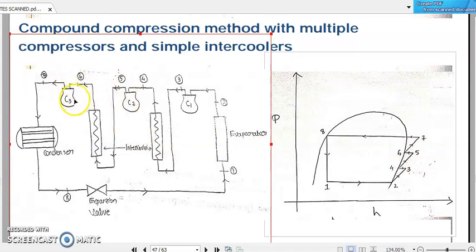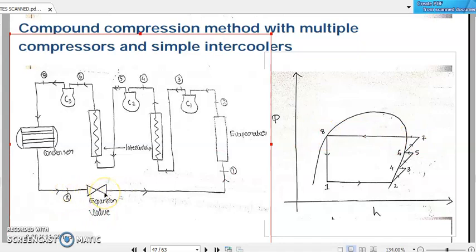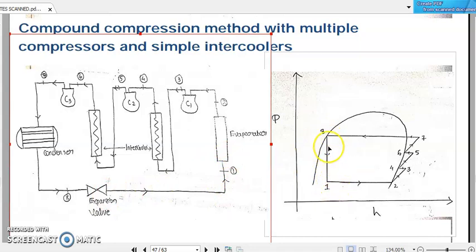Process six to seven is the third stage of isentropic compression, represented as another inclined line in the pressure-enthalpy diagram. From seven to eight, the refrigerant passes through the common condenser, rejecting heat to the surroundings at constant pressure — so seven to eight is a horizontal line. After point eight, the refrigerant passes through the expansion or throttling valve before entering the evaporator. Throttling process eight to one is a vertical line in the pressure-enthalpy diagram, followed by refrigeration process one to two, and the cycle continues.